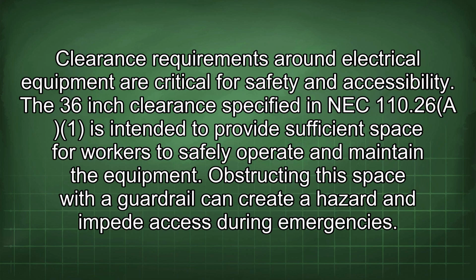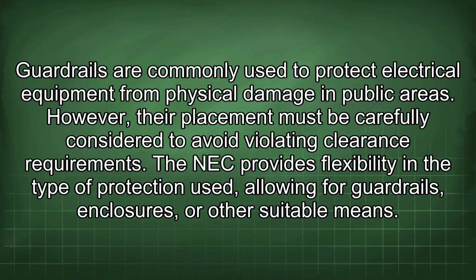Clearance requirements around electrical equipment are critical for safety and accessibility. The 36-inch clearance specified in NEC 110.26(A)(1) is intended to provide sufficient space for workers to safely operate and maintain the equipment. Obstructing this space with a guardrail can create a hazard and impede access during emergencies. Guardrails are commonly used to protect electrical equipment from physical damage in public areas. However, the placement must be carefully considered to avoid violating clearance requirements. The NEC provides flexibility in the type of protection used, allowing for guardrails, enclosures, or other suitable means.